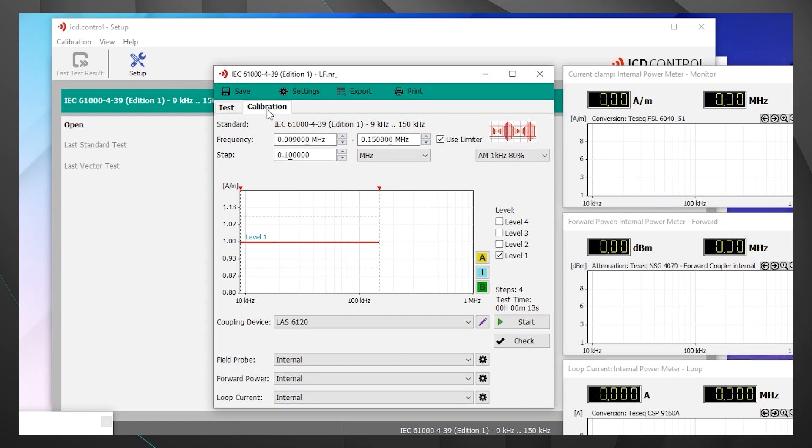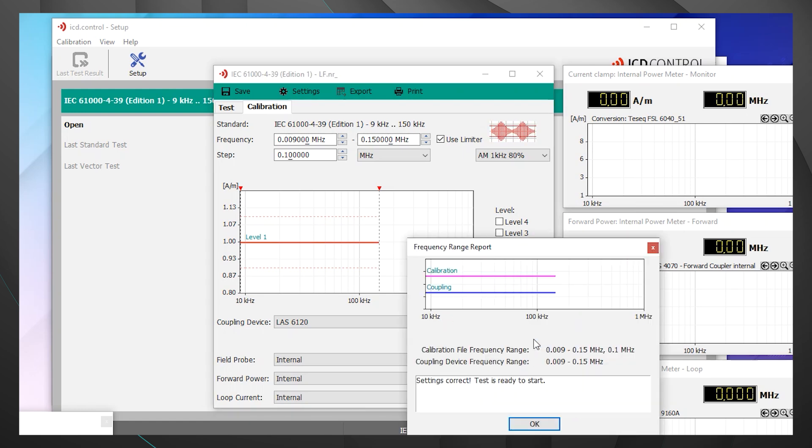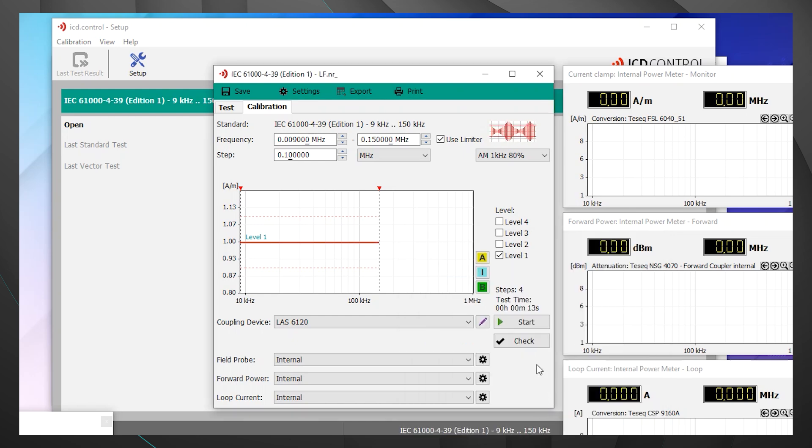Looking at the calibration information here, we have our frequency entered. We have adjusted this step slightly just to allow for a faster calibration for today's video. We kept the default modulation as well as the other criteria in this menu. Now let's look in the bottom right corner. There you'll see the start, and then below that, check. If you click that check, it's going to verify your setup. Just like that, you'll see a pop-up box at the bottom: Settings are correct, test is ready to start. So now let's run our calibration.